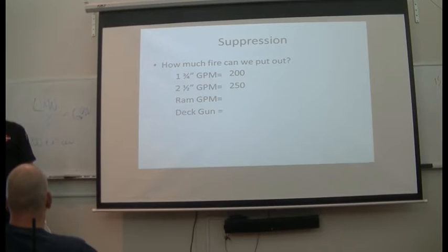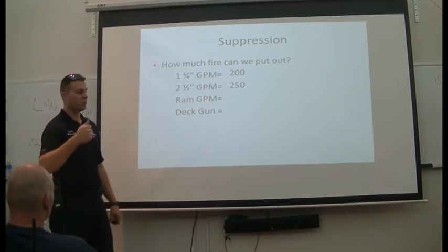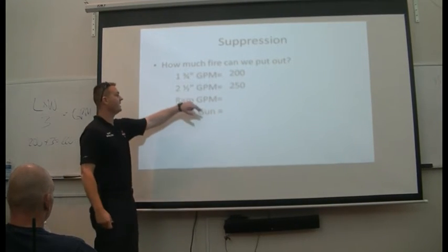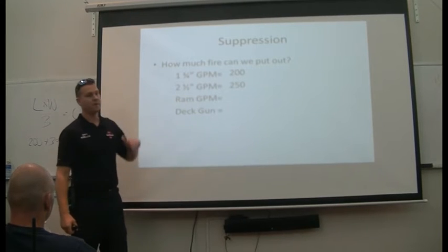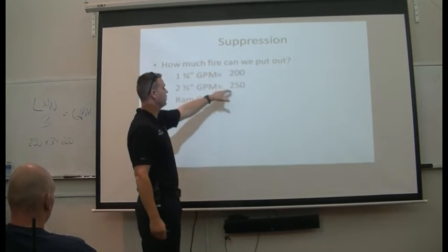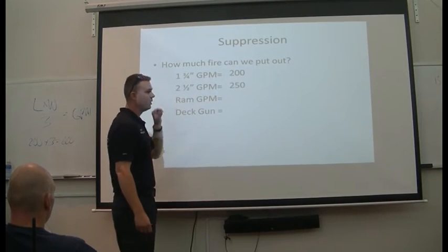Gallons, we need water, and reach. Pressure and reach, right? Commercial occupancies, pressure and reach. Do we get that with a combination nozzle and 2.5? The same line with a solid bore nozzle can do up to 380 gallons per minute with further reach.